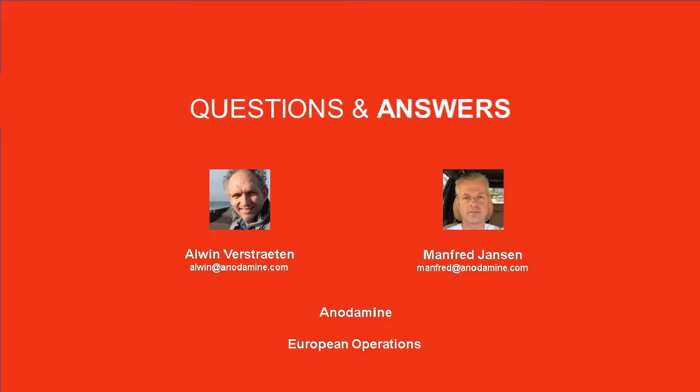Yes, hello everyone. Thank you, Manfred, for the presentation. A few questions came in via the chat, and let's discuss the first one, Manfred. First one is: we have a triple pressure HRSG which contains an HP steam pressure of 170 bar and a temperature of 586 degrees. Can we use anodamine? Well, I already mentioned that we run a lot of subcritical units, and they have higher steam temperatures, higher pressures, even condensate polishing filters. So it's definitely yes for this one.